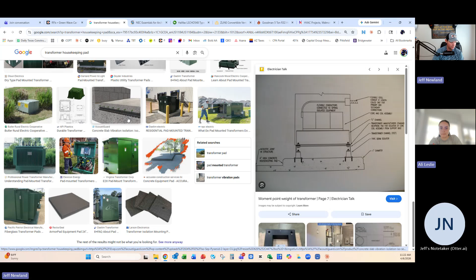Let's see here, roof curb sets. Verified dimensions match equipment submittals. That's fair. So if we do have a housekeeping pad that is called out, you'll want to look at the condensing unit or the RTU or whatever piece of equipment, doesn't have to be a condensing unit, and make sure the pad's big enough. That's all you're kind of looking at. You can go ahead and send in an RFI and we can expand it and all that kind of good stuff.